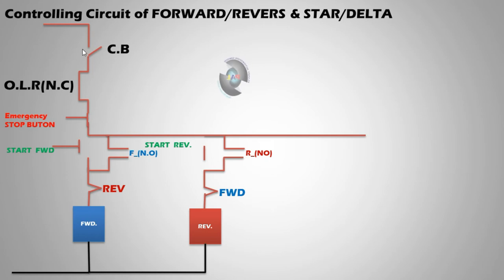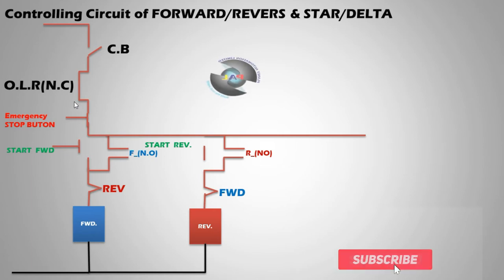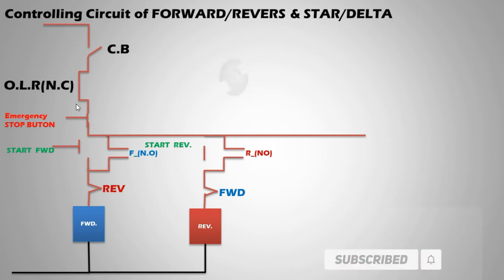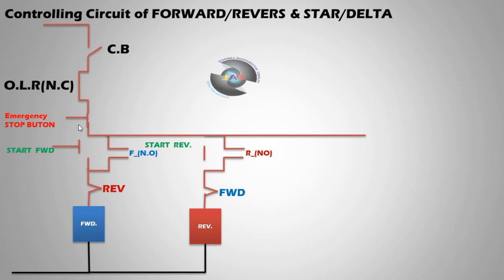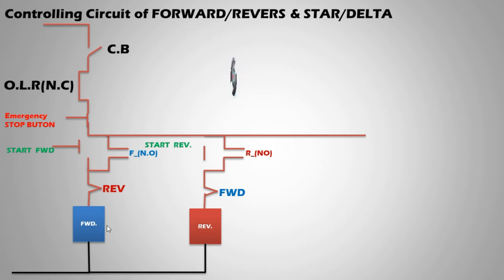The output is connected to pin 95 and 96 of the overload relay, going to the emergency stop button, then to the start-forward button which is connected in NO condition and latching for the push button. This keeps the contactor latched ON all the time. When we start forward, the motor will run in forward direction.